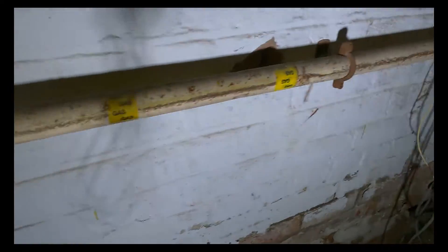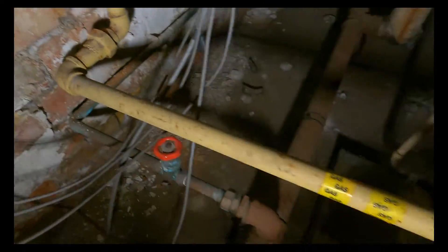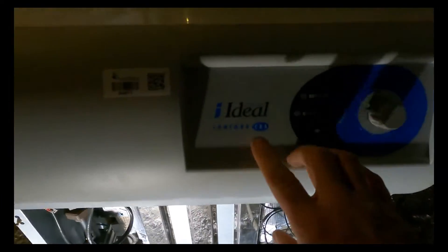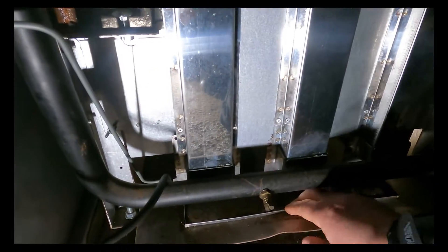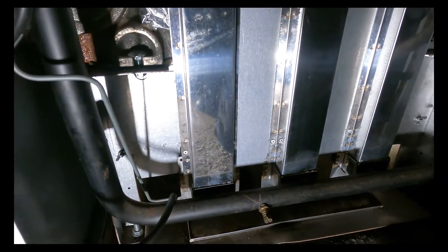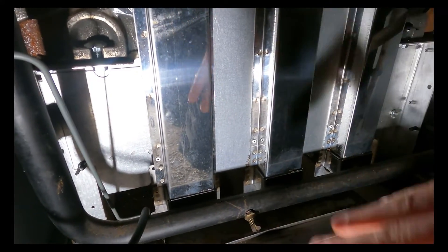And it just comes along, back down, all the way through, back to the boiler with local isolation - we'll all need to turn that off, so we'll reinstate that. We'll carry out a strength test first. What I'll do with this one is just do a 1 bar test according to the calculations. We've got in here the Ideal Concorde CXA boiler - neat little bit of kit. It's an atmospheric burner, so just the burner bars underneath here. As the demand on the boiler comes in, the switch live will come in, the pilot will be lit by electronic ignition, and it'll just ignite and away she goes, and she'll keep going until the stack reaches temperature.